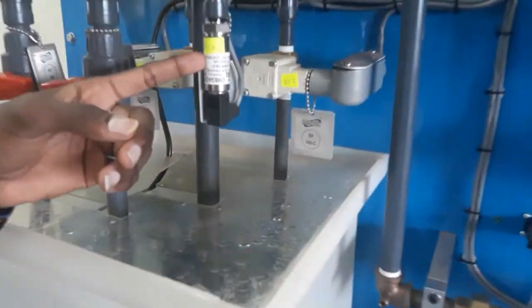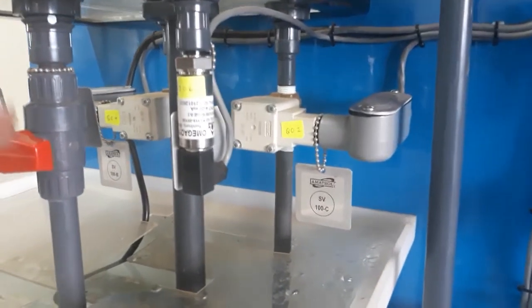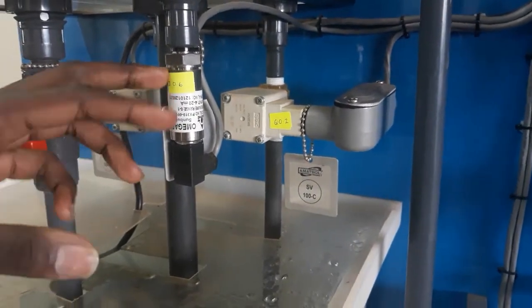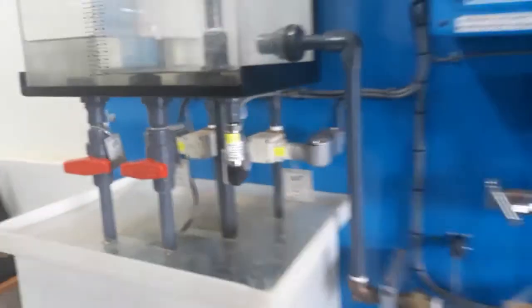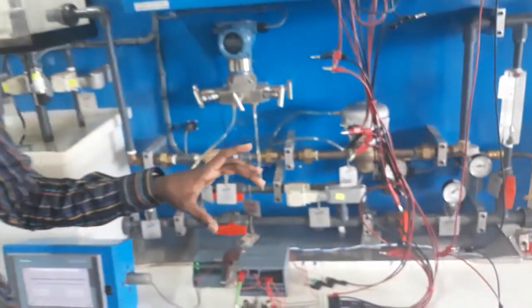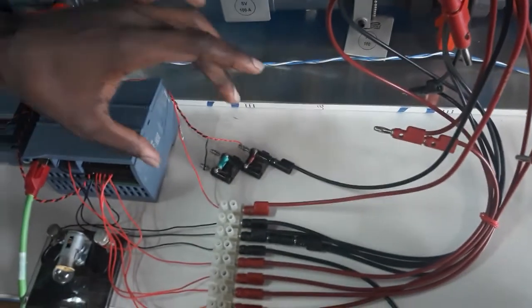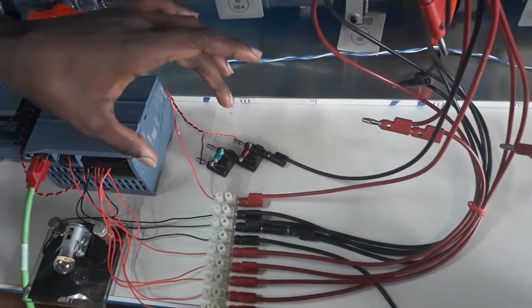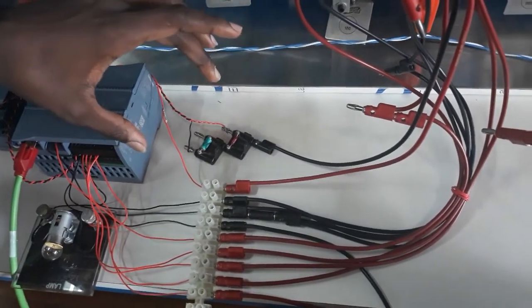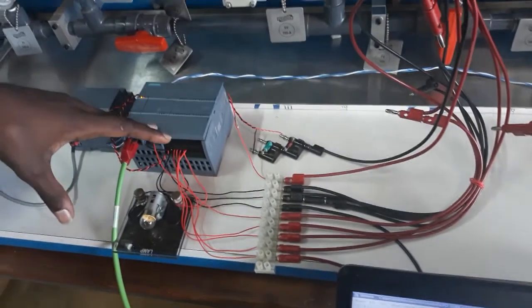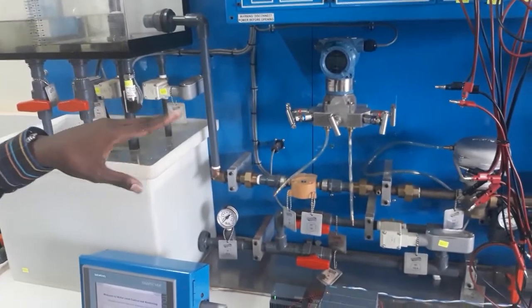This is our first input, an analog input, a pressure sensor. This analog input gives a current signal to the PLC, and the PLC requires a voltage signal. So from the analog input, we have to connect it via a 500 ohm load. Using Ohm's principle, V equals IR, from the load we can get a voltage value which goes straight to the PLC. The analog input is connected to port 64 of the PLC.